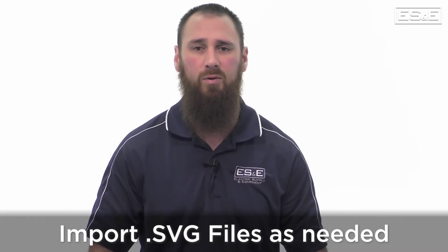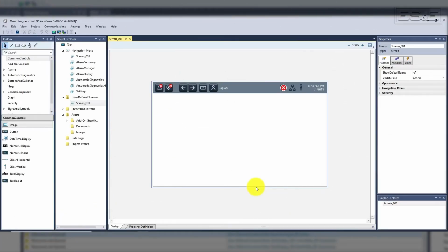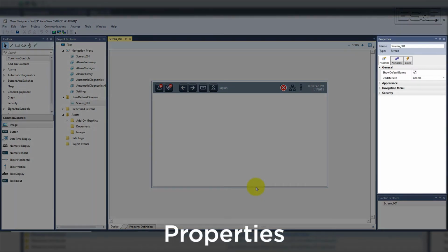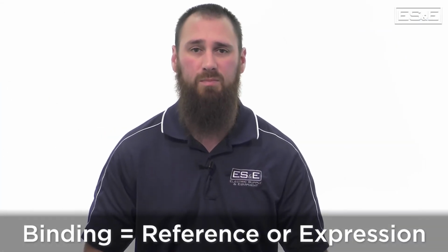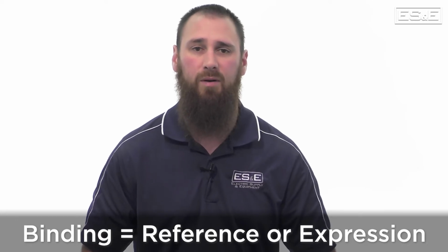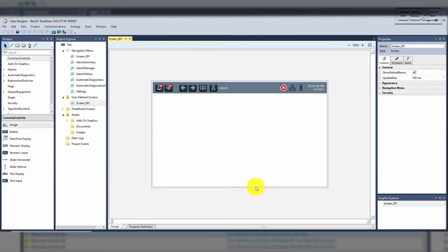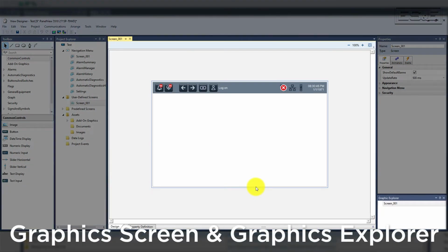to create new objects. Another major area is the property window, which contains your standard properties, animations, and events for each object. View Designer allows you to configure each property or add a binding. A binding can be a simple tag reference or a full expression to modify the property from the PLC. The property window is the key area to configure an object to look and do what you want it to do. The last two areas are the graphics and the graphics explorer.